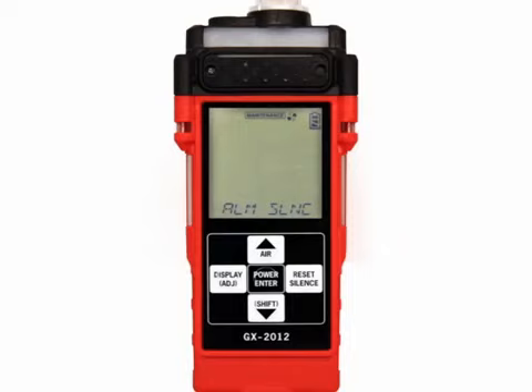If an alarm condition occurs, you may still enter display mode by pressing the Display Adjust button. The buzzer will be silenced, but the LEDs will continue to flash and the unit will continue to vibrate. If you return to measuring mode and there is still an alarm condition, the LEDs will continue to flash, the unit will continue to vibrate, and the buzzer will remain off. Once the condition clears, press the Reset Silence button to clear the alarm indications.